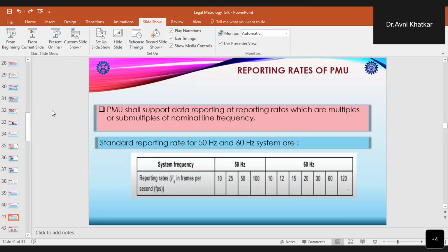Now, when we talk about PMUs, they have different reporting rates as per the need of the application. PMUs support different data reporting rates. However, these should be multiples or sub-multiples of the nominal line frequency. And the standard reporting rates for 50 hertz and 60 hertz systems are shown in this figure.